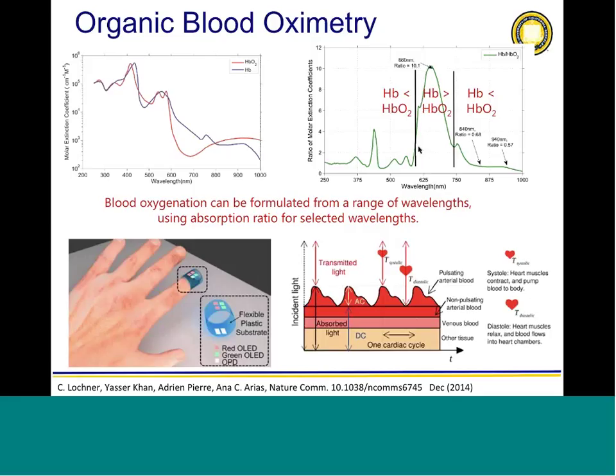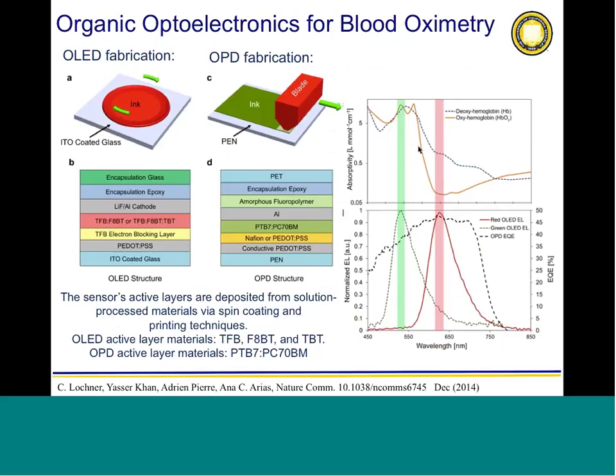For the electrical engineers here, when you are measuring pulse oxygenation, you have the pulse, and that's the signal that you want to pick up. But the light also goes through bone, through tissue, and through blood that's not pulsating, and all that contributes to a quite large DC signal in your measurement. Then you have a little AC signal oscillating on top of the DC signal, which carries the pulse information. So for pulse oximetry, you have to pick up this AC signal. If you just want to know the saturation of oxygen in the blood, you can measure in other locations where you don't have the pulse. But you always need the pulse to calibrate your measurement, and I'll go back to that later in my talk.